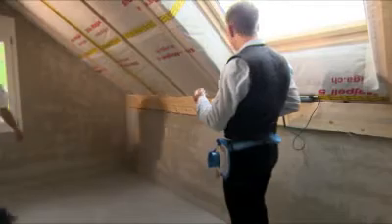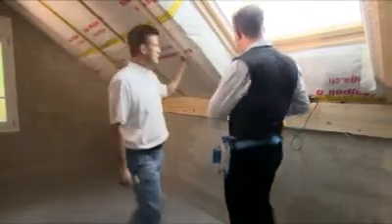Smoke escapes in the area of the skylight. It is not the skylight itself that is leaky, but the joint between the vapour control layer and the skylight frame.